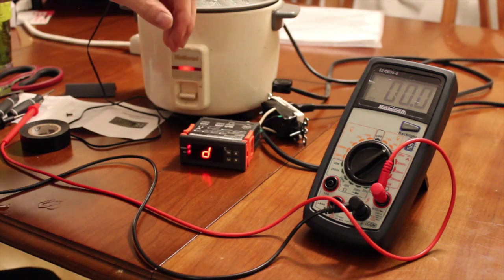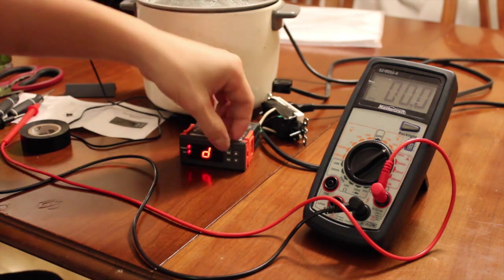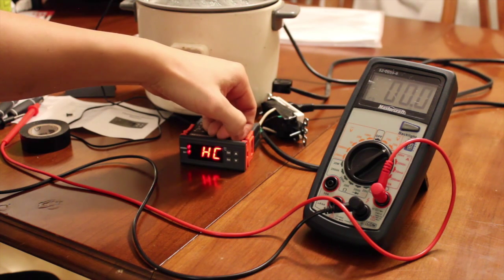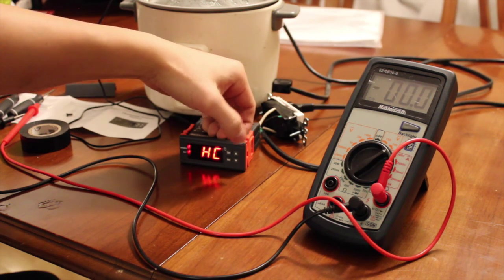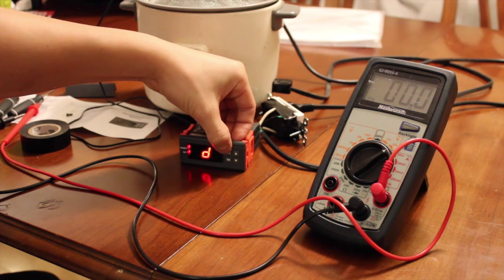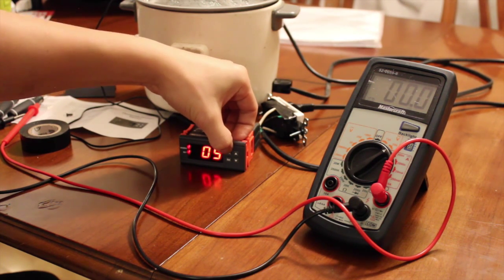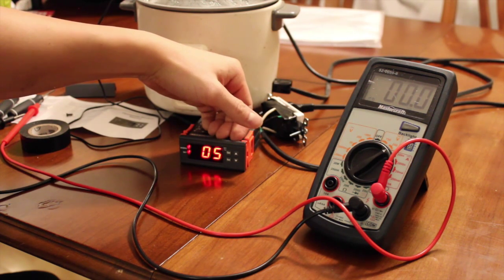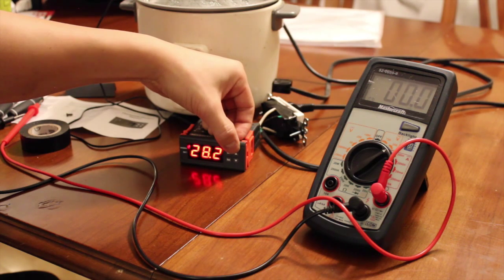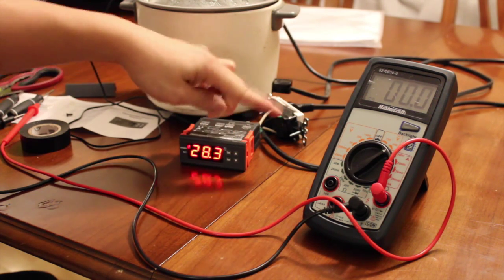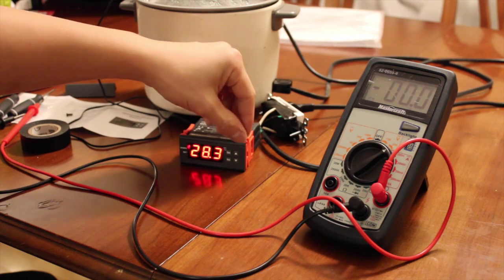D is hysteresis. Hysteresis means that if I set it to 60 degrees and we go to 60, it will turn off the machine. And since I set it to 5 degrees here, it won't turn back on until it's 55 degrees, which is 60 minus 5. This is so that you don't have a quick switching right around zero.